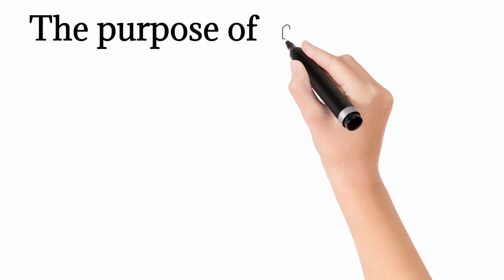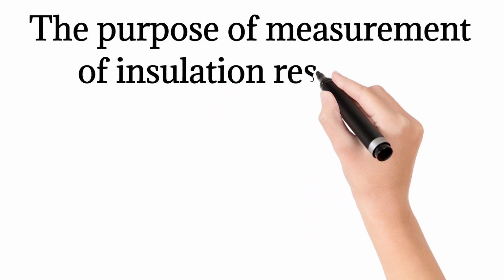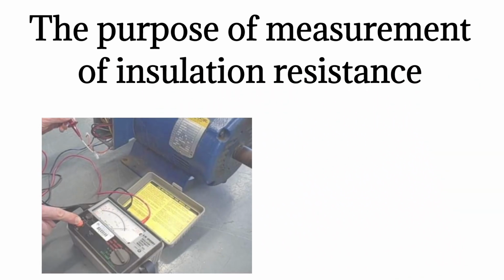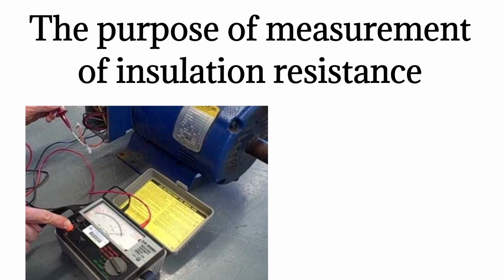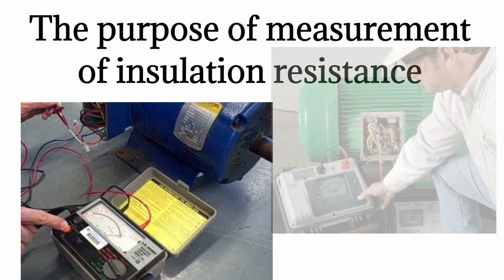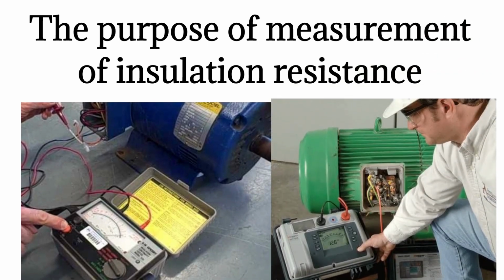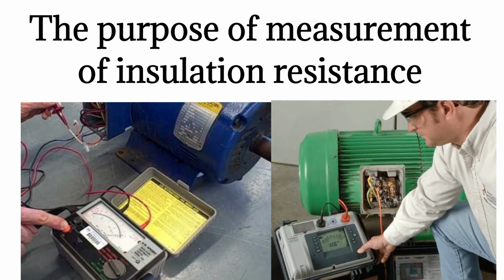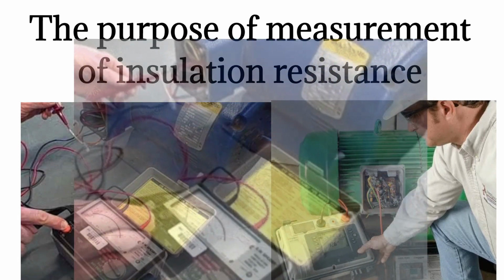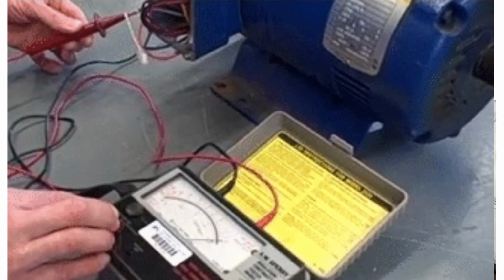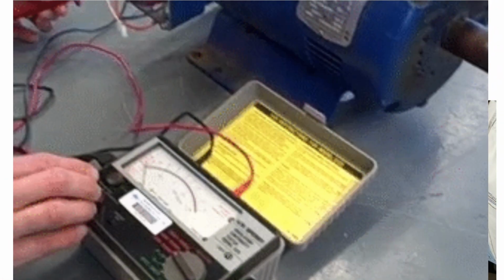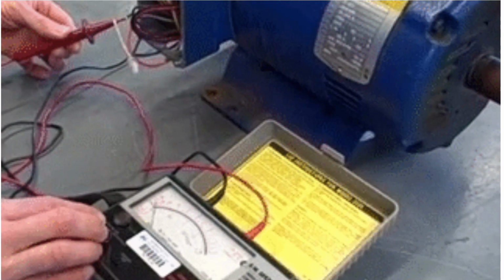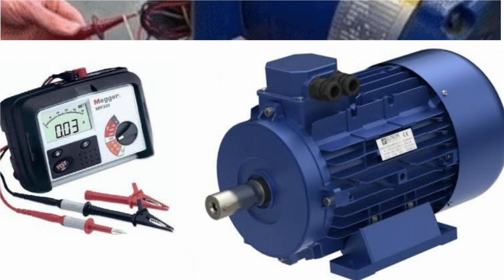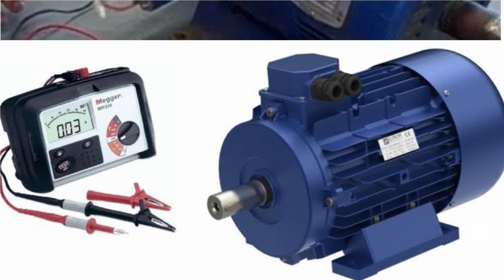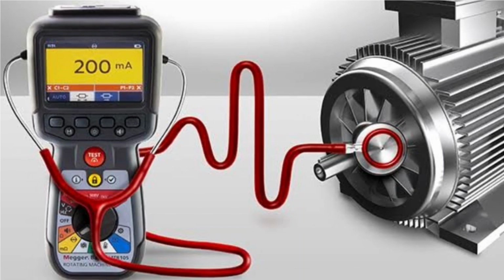The purpose of measurement of insulation resistance. Measuring the resistance of motor windings makes it possible to detect deterioration due to weather, corrosion, dirt, moisture, and excess vibration before the motor fails. There are very clear limitations on the ability of insulation resistance testing alone to assess the condition of an electric motor for operation. One thing to be taken care of is that there has to be a clear path between the insulation system and the machine cover.